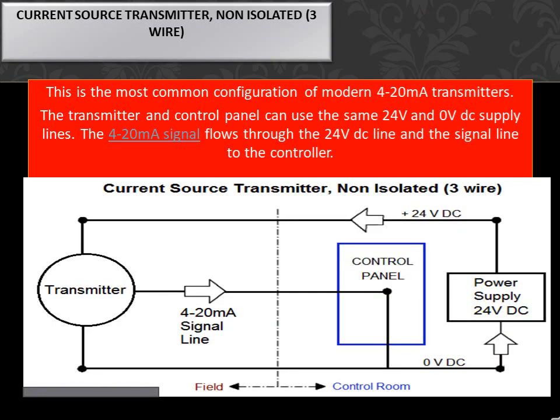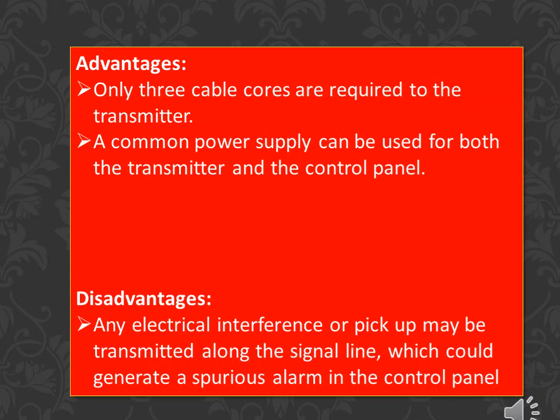Current source transmitter, non-isolated, 3-wire. This is the most common configuration of modern 4-20mA transmitters. The transmitter and control panel can use the same 24V and 0VDC supply lines. The 4-20mA signal flows through the 24VDC line and the signal line to the controller. Advantages: only 3 cable cores are required to the transmitter, and a common power supply can be used for both the transmitter and the control panel. Disadvantages: any electrical interference or pickup may be transmitted along the signal line, which could generate a spurious alarm in the control panel.